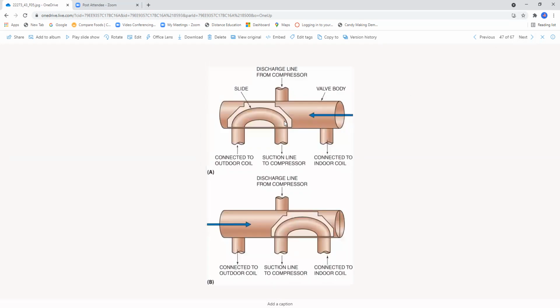Okay, we talked about this in the PowerPoint presentation. This thing here is the mechanism that's going to slide over from heating to cooling. So for cooling, notice here, you're going to see this app, and I believe, just for your information, it is in your textbook. We talked about it this morning, but we'll talk about it again. This is extremely important if you do not understand the four-way valve process. This particular one is located on page 1276 under figure 43.5. So the internal slide of the four-way reversing valve solenoid determines the position of the slide. Most systems operate in the heating mode when the solenoid is de-energized. A is the position of the slide when the solenoid is de-energized. B is going to be the position of the slide when the solenoid is energized. So de-energized, energized, okay?